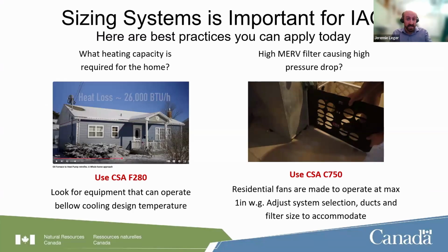Sizing your system is important for indoor air quality, and there are best practices you can apply today. The first is sizing your equipment to the cooling loads, using CSA F280 to know the heat loss and heat gain, the cooling and heating load of your house, as a first step in any mechanical retrofit.